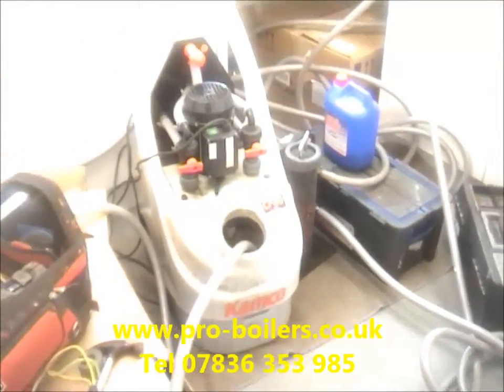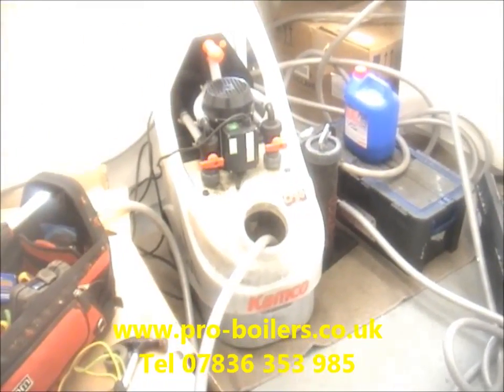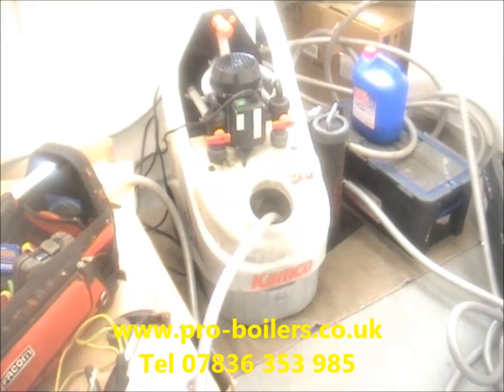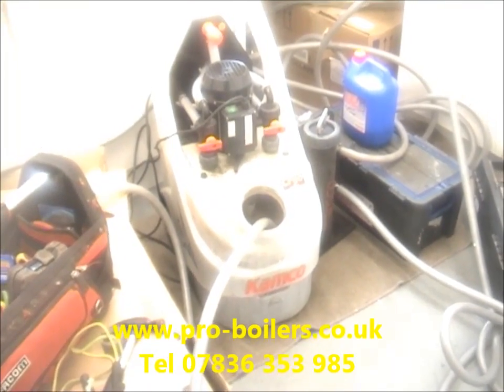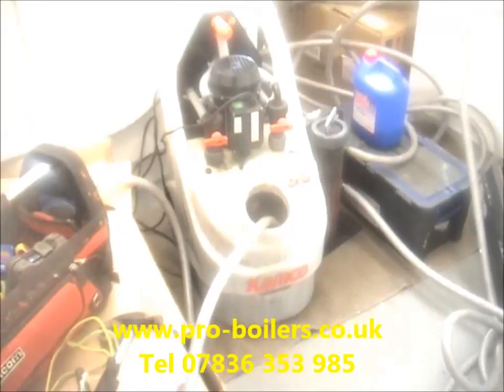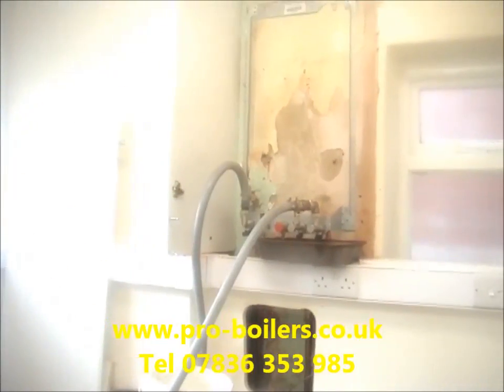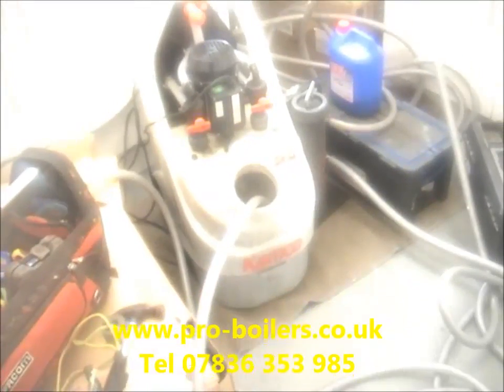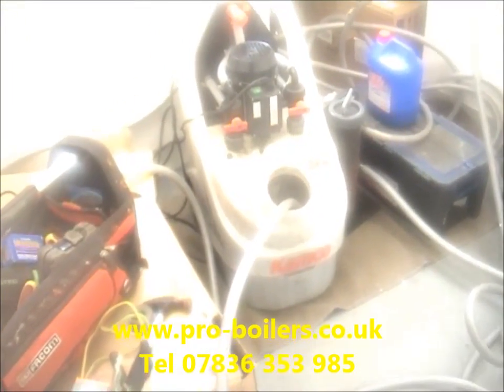Hopefully you can see this video - the camera got a bit cold, it might be a bit misty, but there's loads of rust and sludge in this system. We're doing it properly because we've hooked in to where the boiler's going to go. The boiler's not hung on the wall yet, so every part of this system will be thoroughly cleaned before we put the boiler in.